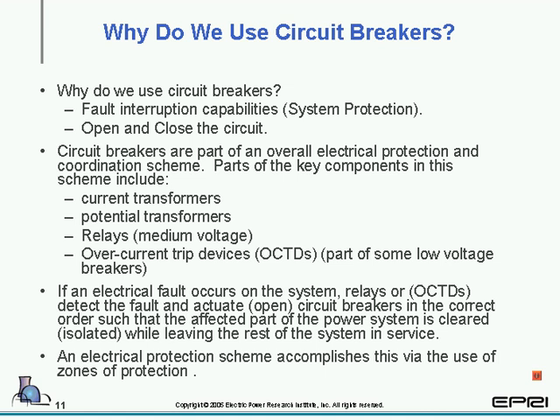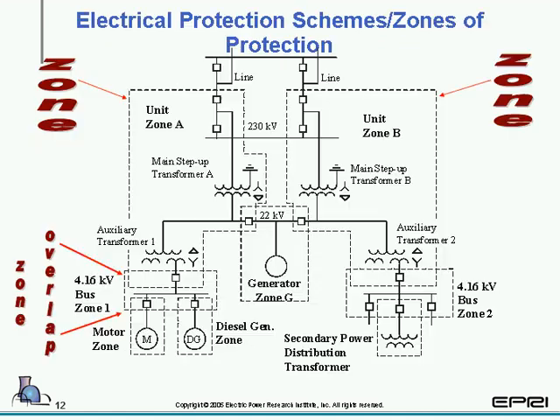One of the ways this is looked at is that the electrical protection scheme is accomplished via the use of zones of protection. And here we have a slide that shows the actual zones of protection. We have zone A, we have zone B. They then feed down, and you're going to look over on the left-hand side, and we have overlapping zones from the 4160 V bus zone 1 to the motor zone and the diesel generator zone.